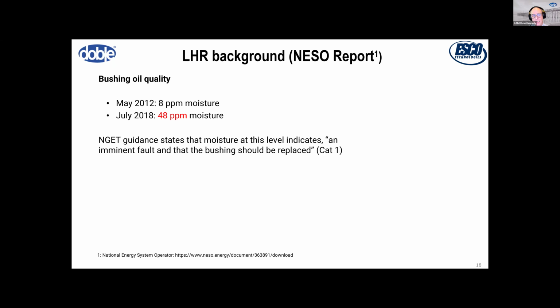Now the NGET guidance, that's the National Grid Electricity Transmission, their organizational body there in the UK, states that moisture at this level indicates an imminent fault and that the bushing should be replaced. It's a category 1 as set in their procedures for NGET.